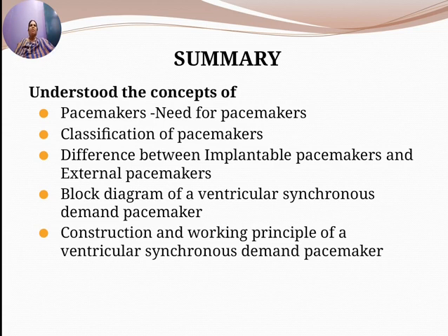The output of the timing circuit is fed into the pulse width circuit, which is also an RC network. The pulse width circuit determines the duration of the pulse delivered to the heart. Then the output of the pulse width circuit is fed into the rate limiting circuit, which limits the pacing rate to a maximum of 120 pulses per minute. The output circuit provides a proper pulse to stimulate the heart. Thus the timing circuit, pulse width circuit, rate limiting circuit and output circuit are used to produce the desired pacemaker pulses to pace the heart.